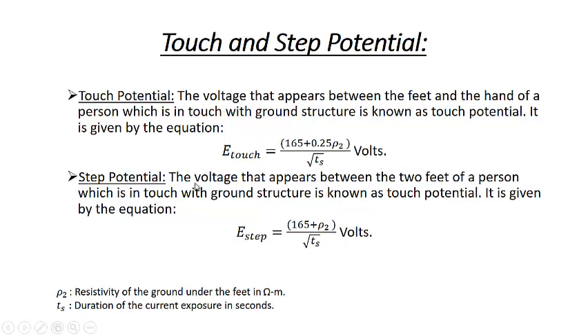Now the step potential: the voltage that appears between the two feet of a person who is in touch with the ground structure is known as step potential. It is given by the equation E step = (165 + rho 2) divided by the square root of Ts volts. In this case, rho 2 is the resistivity of the ground under the feet in ohm meter, and Ts is the duration of the current exposure in seconds. Now, why are these two potentials very important?